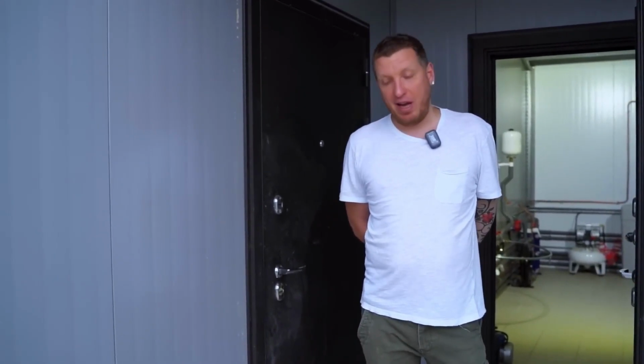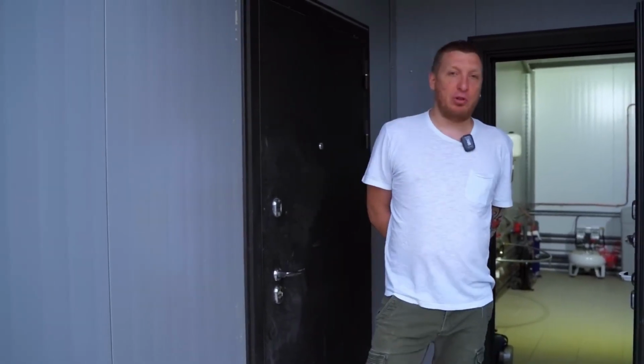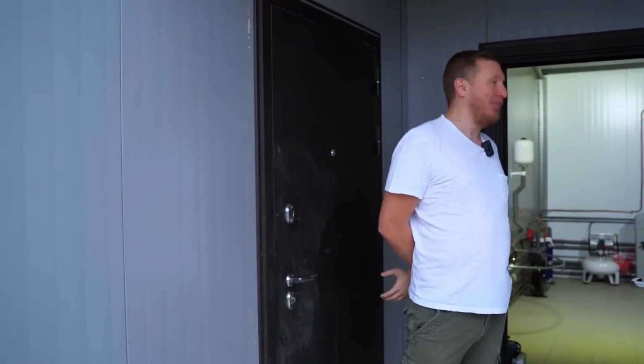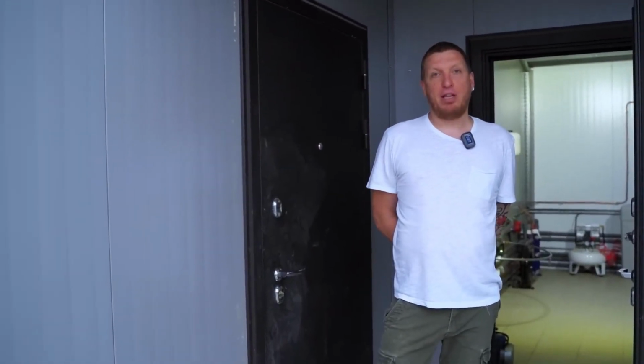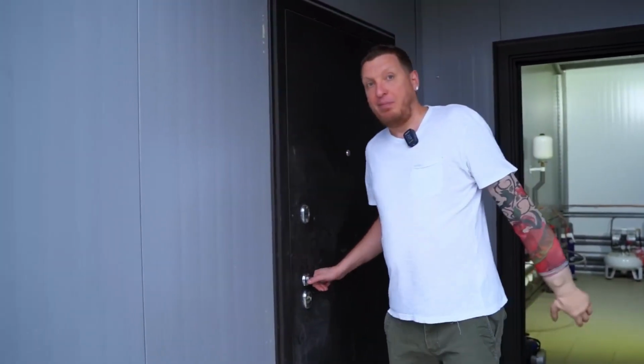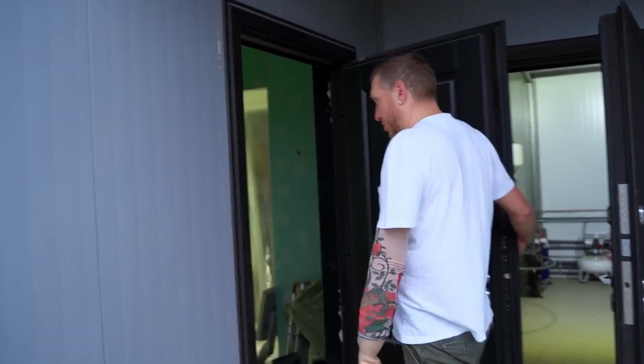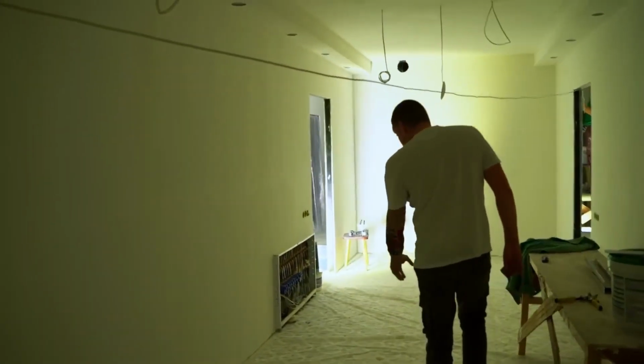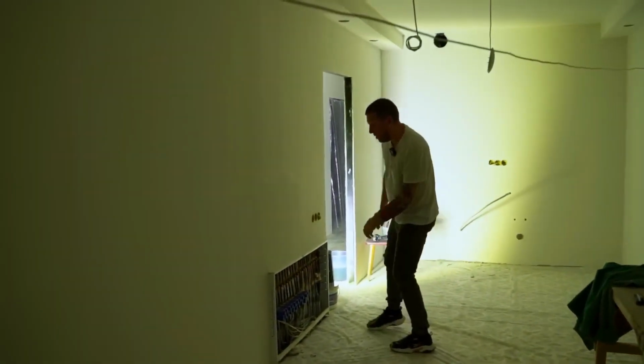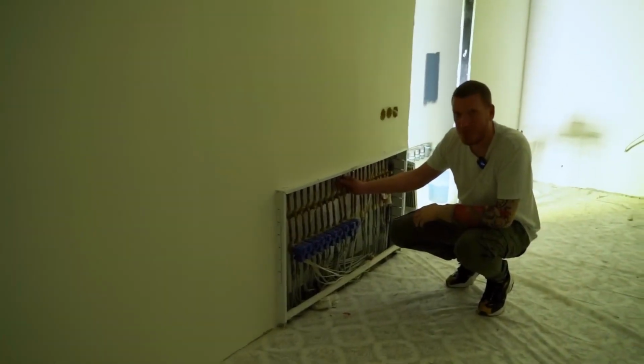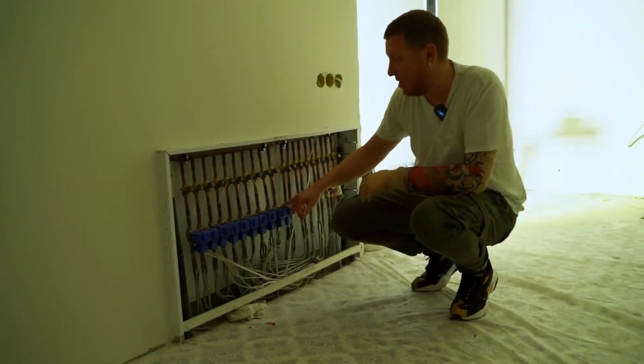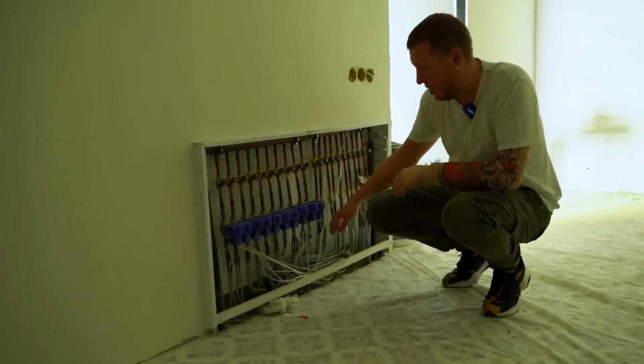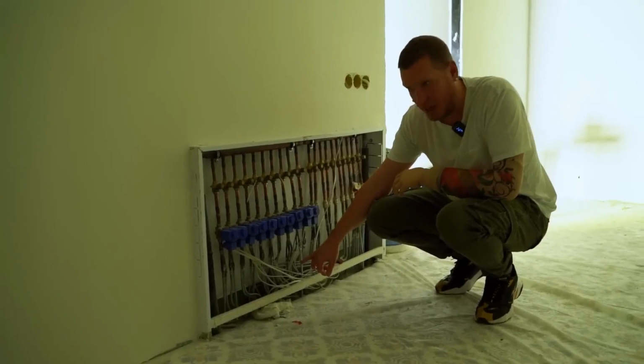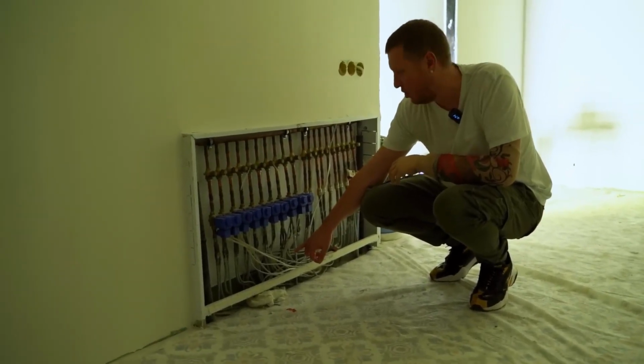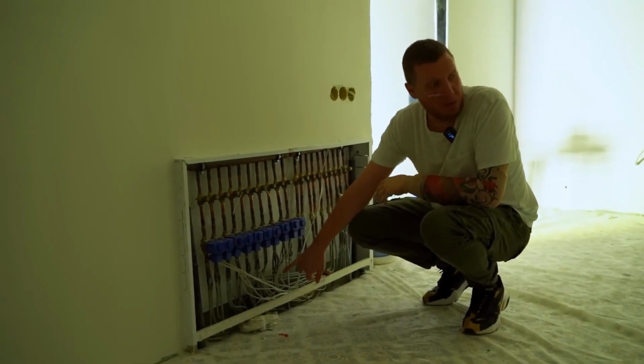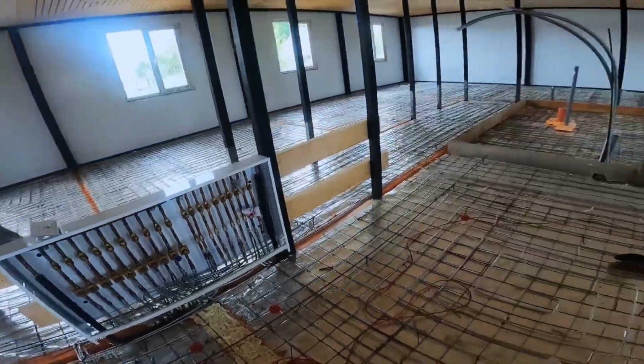In this mode, for every kilowatt of electrical energy consumed, with low condensation at around 30 degrees, you get 5 kilowatts of heat, which is very efficient. Let me show you where all of this goes next. Here, finishing work is still underway, and this is how the heating system is set up. It comes to the manifold, which has solenoid valves. There are also check valves here, and this pipe transitions into a galvanized steel pipe, because using copper would be very expensive. There are about 2 kilometers of this pipe running under the floor everywhere here.